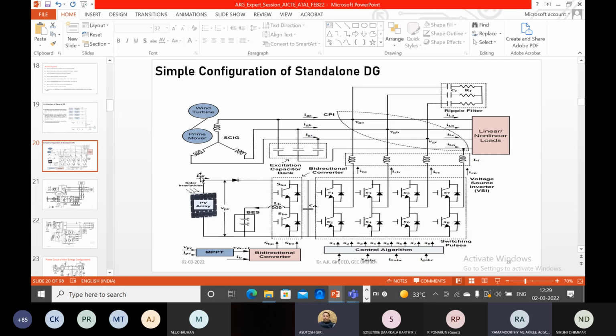When you are doing the control design, you have to additionally consider the component of the PV, the real power component of the PV. And when we are calculating the real power, because we are maintaining reactive power from this side, the DC link capacitor is there - it will be able to supply the reactive power support to the load. But the only thing is, when we are creating a reference current for supplying the real power from the generator, we have to subtract this current from the load current. Are you getting my point?